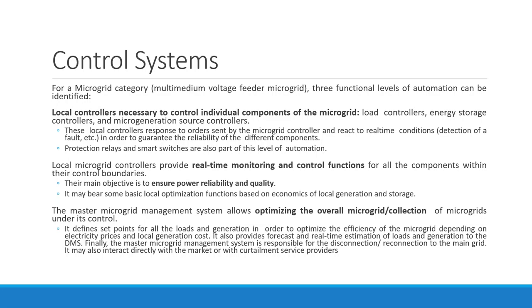Suppose a fault is detected. At that time a signal will be sent by the microgrid controller to a sub-controller that now you have to act. This guarantees the reliability of the different components. Protection relays and smart switches are also part of this level of automation. We are talking about the load controllers. Local microgrid controllers are going to provide real-time monitoring and control functions for all the components within a boundary. A boundary will be there, and whatever components are within that boundary are covered by the local microgrid controller, and possibly there may be more than one.